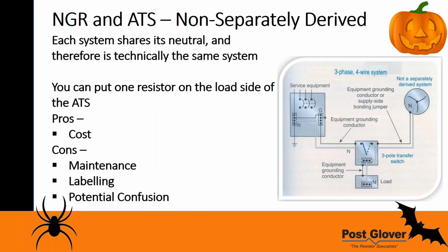Let's talk about non-separately derived systems. The NEC treats it as basically the same system, with two separate sides, but instead of switching a 4th pole, you have a direct contact, so you just use a 3-pole transfer switch, transferring only the three phases. Because you're sharing that neutral, just like with parallel generators, you run into maintenance issues—you essentially have to turn off the whole system to maintenance this unit.